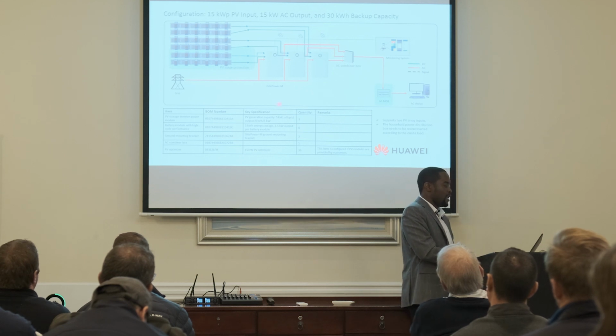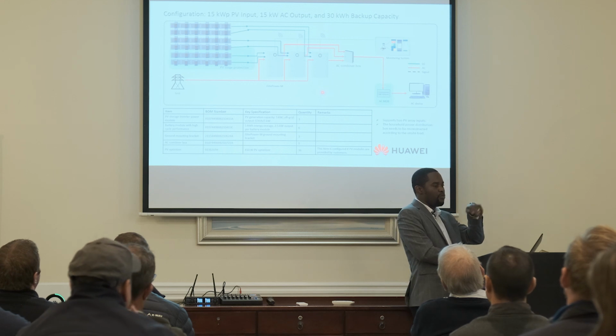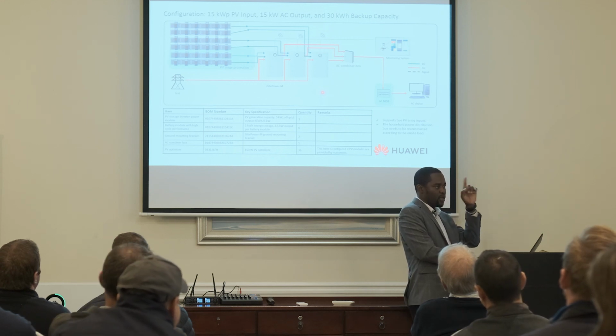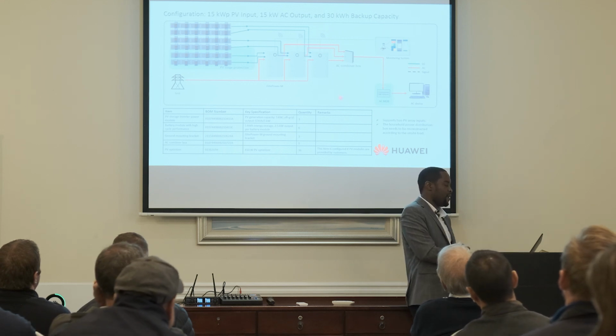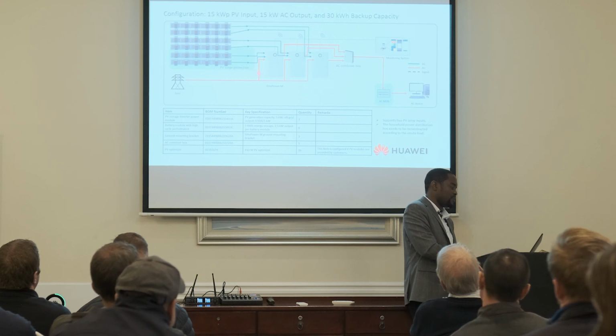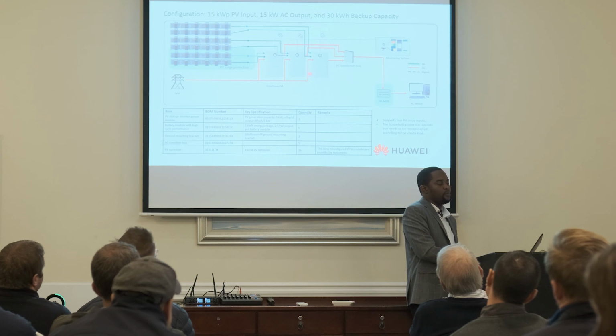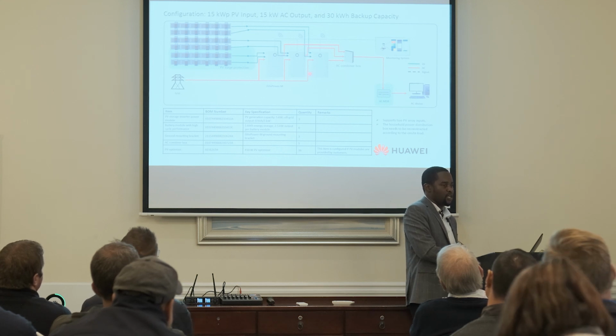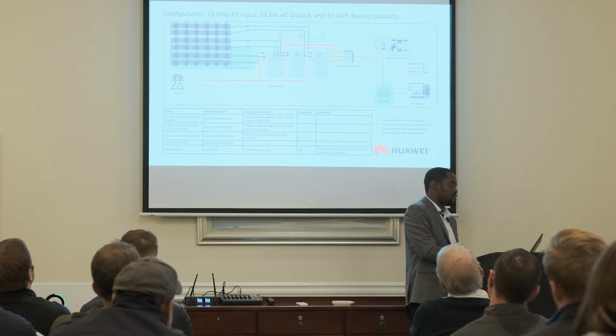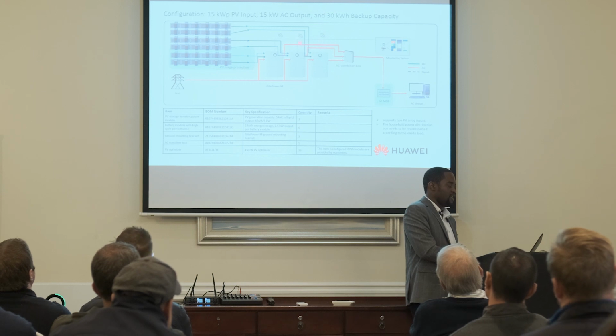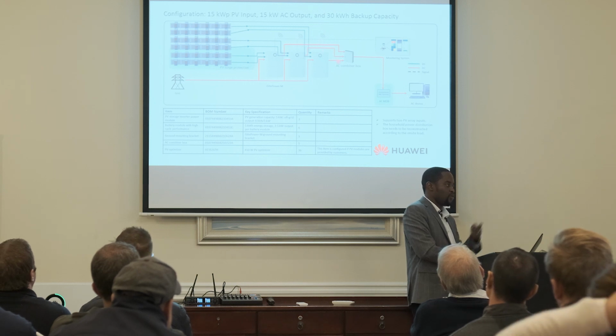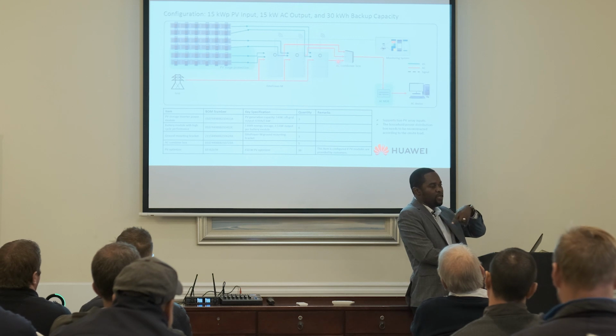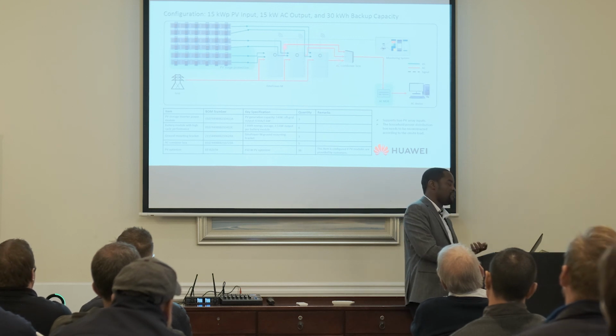We greatly recommend that when you are paralleling, remember it's a common grid, which means you can actually loop your grid inputs, your earth, your live and your neutral. But we greatly recommend that you put a breaker here. You put a breaker at this point so that you are able to isolate each inverter individually, right? The same applies to the AC output. It's wise to also put breakers on the output, even though you can actually loop it, but you can put a breaker on each for maintenance purposes.